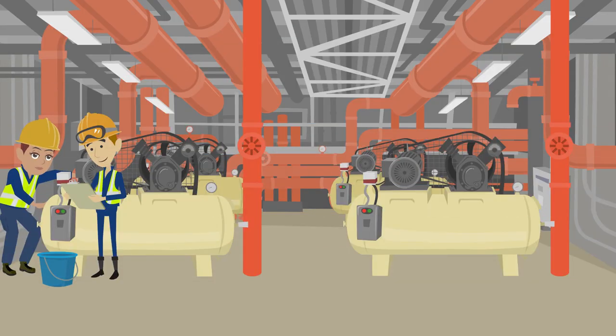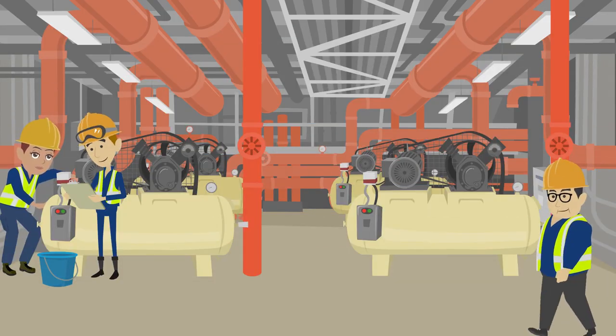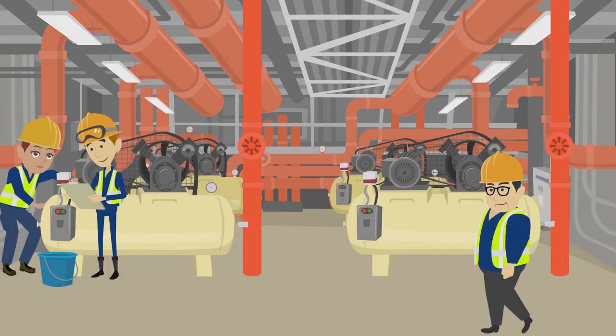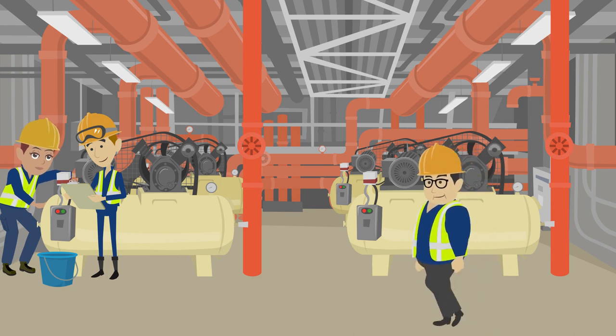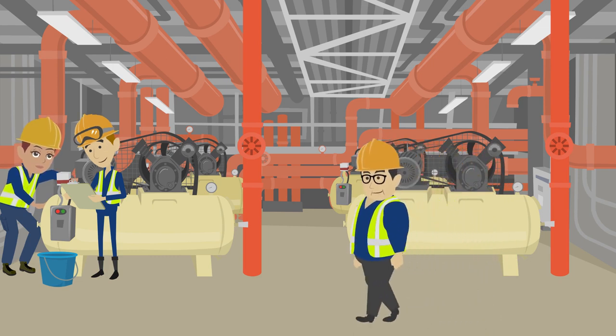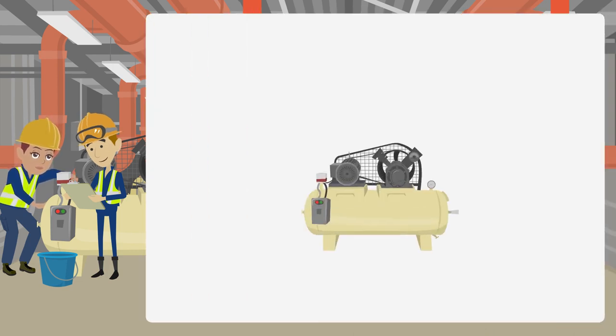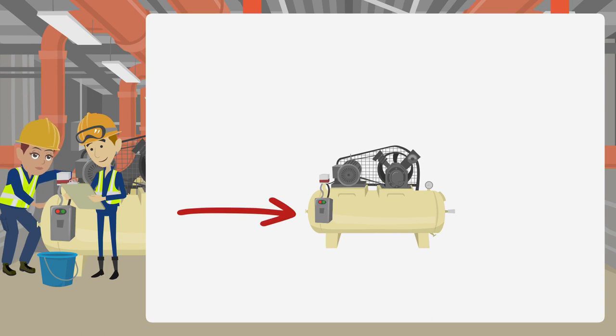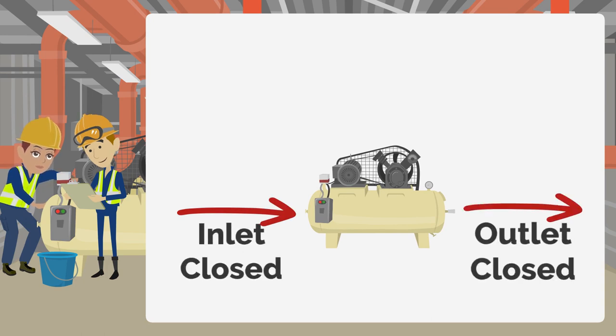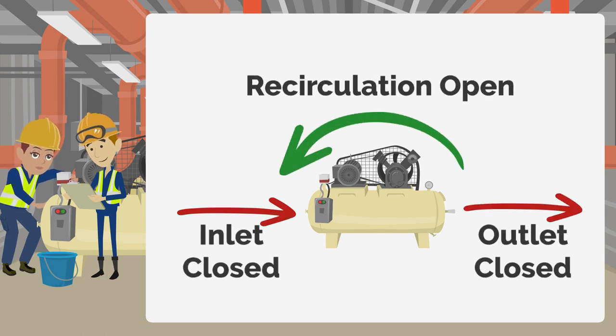Settle-out occurs at compressors and pumps when inlet and outlet pressures reach equilibrium. An overpressure is credible if the following are true: first, there is a credible scenario where the inlet and outlet of the compressor could be closed with a recirculation line open.